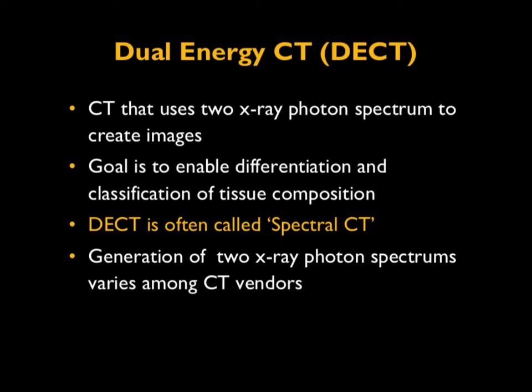Even though spectral CT in reality means a multi-energy CT, for now dual-energy CT is also called spectral CT. The purpose of this discussion is to see how dual energy is achieved — that is, how the generation of two x-ray photon spectra is achieved — which varies among different CT vendors, as each vendor has taken a different path.